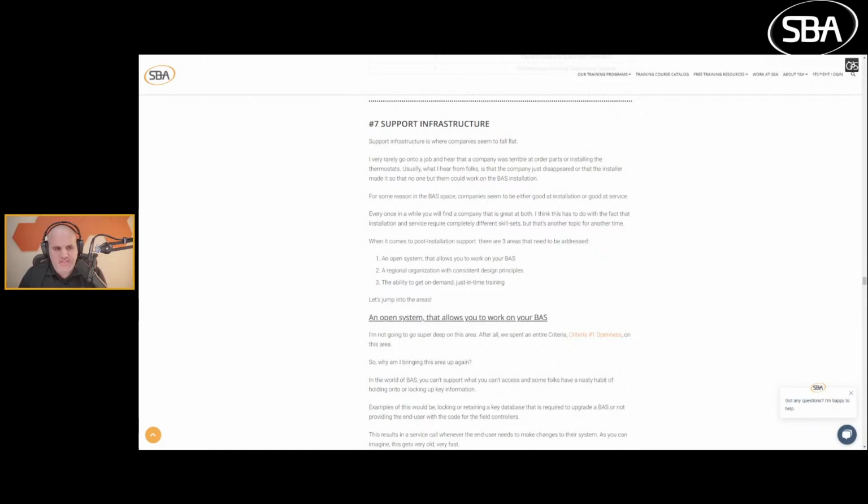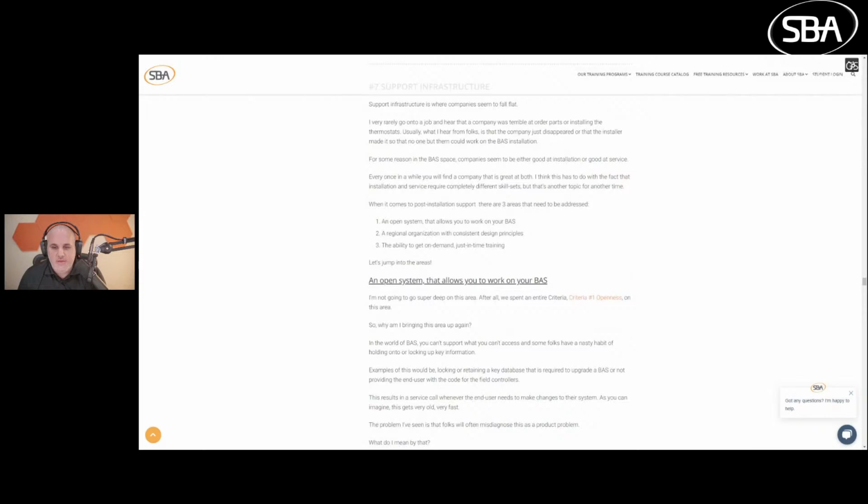It's like 18 months, if I remember correctly. That's when building automation systems start to degrade via overrides, sensor calibration issues, PID tuning issues, etc. And you want to make sure you have someone there to guide you through that so you don't find yourself in for a world of hurt.